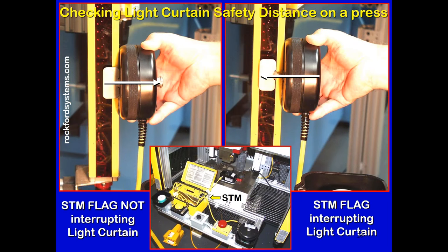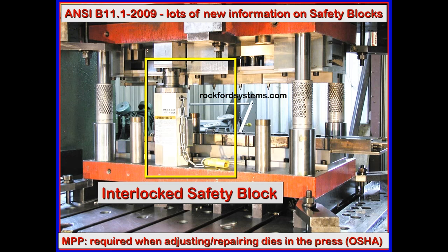This is a portable stop time measurement safety device designed for calculating the stopping time, which when plugged into a formula will give you the safety distance for light curtains or two-hand controls. If you have a newer control system manufactured in the last 15 or 20 years, you probably have a built-in stop time measurement device. If you have older controls, like relay logic controls, you probably need a portable device like this one. So you could purchase a device like this, or you could contract the service done. I know we have a service that does that here at our company to do stop time measurement tests.